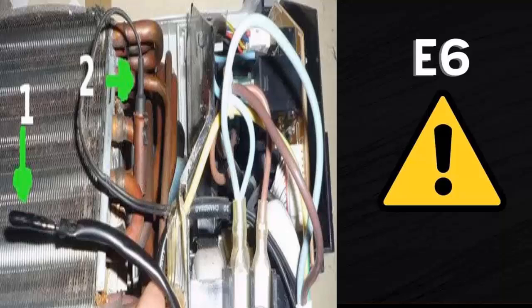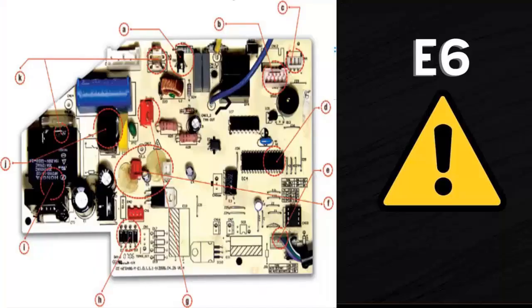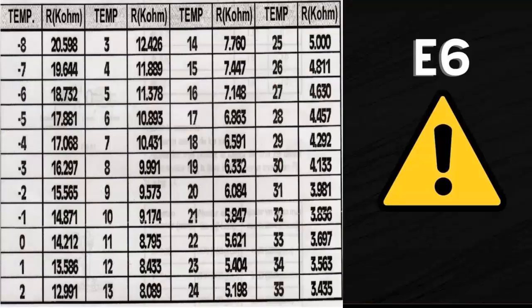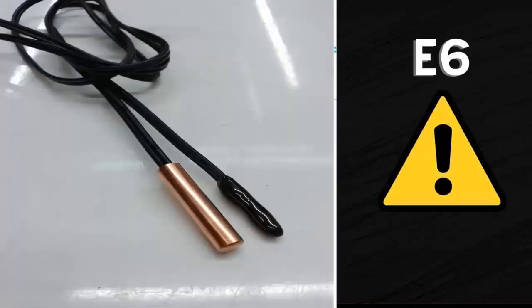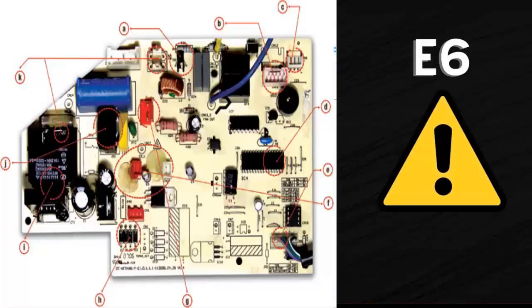The temperature sensor is an electrical resistance that receives electrical current from the control card or board. The electrical resistance of the sensor changes when the temperature changes, causing a voltage change in the electrical current supplied by the electronic card. This voltage change is detected by the card or electronic board, which uses this information to adjust the cooling or heating power.